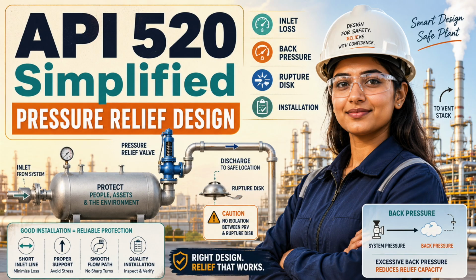For many conventional installations, non-recoverable inlet pressure loss is normally controlled to a small fraction of set pressure, commonly around 3%, unless a justified engineering basis supports another arrangement. This is not a cosmetic design rule, it is a stability requirement. You reduce inlet loss by shortening the line, increasing diameter, removing unnecessary fittings, smoothing the entrance, reducing restrictions, and evaluating the line at the rated relieving capacity.